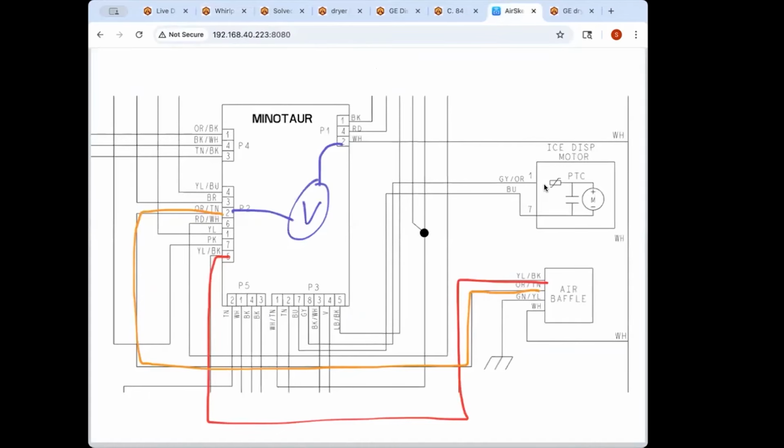So yeah, this guy's next step would be to do this test that we've drawn in here and see if he's seeing anything. Obviously, if you are getting the voltage signal there and the board is not responding appropriately, that can really only leave the board itself. That means the board's getting the signal, but it's not interpreting it appropriately, and it would be a problem internal to the board.